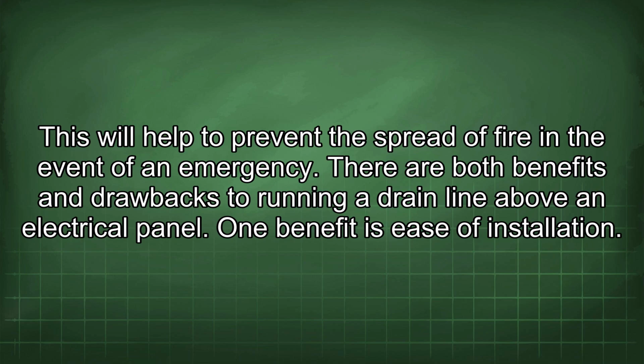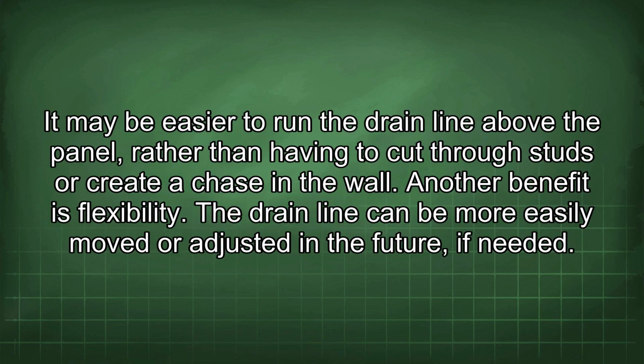There are both benefits and drawbacks to running a drain line above an electrical panel. One benefit is ease of installation. It may be easier to run the drain line above the panel rather than having to cut through studs or create a chase in the wall. Another benefit is flexibility. The drain line can be more easily moved or adjusted in the future if needed.